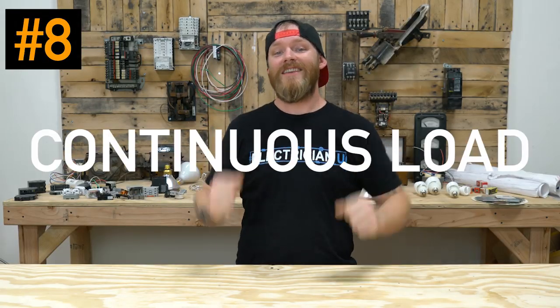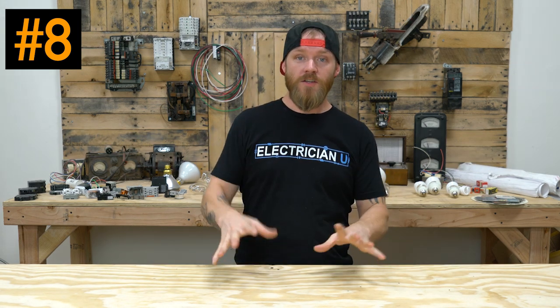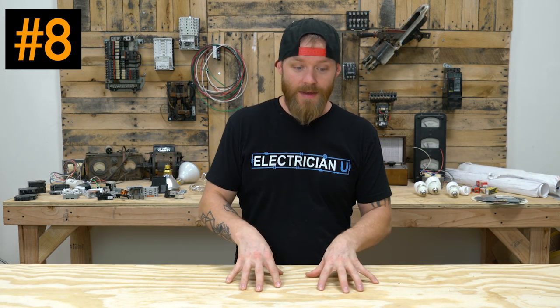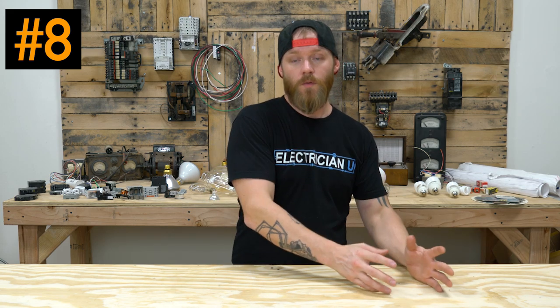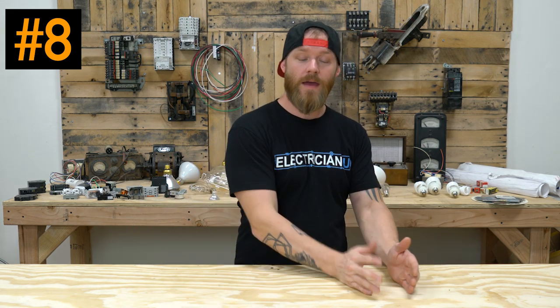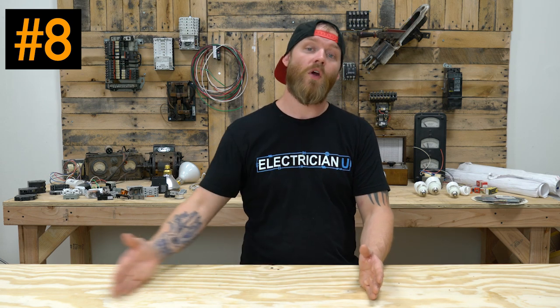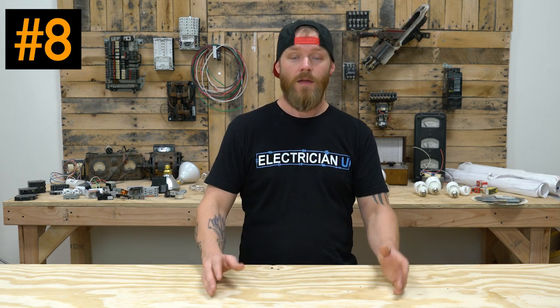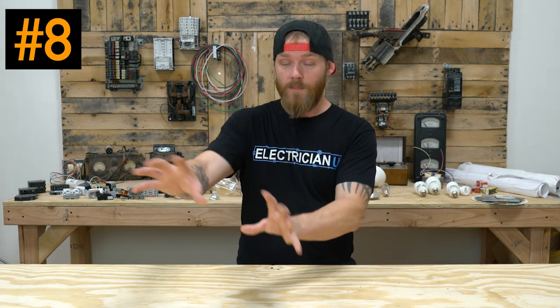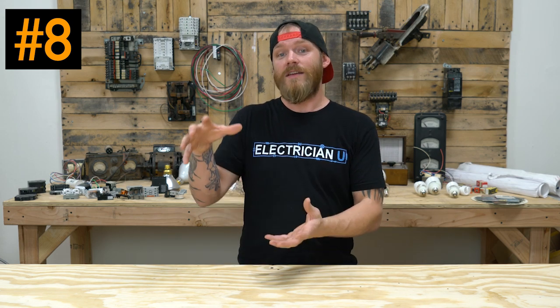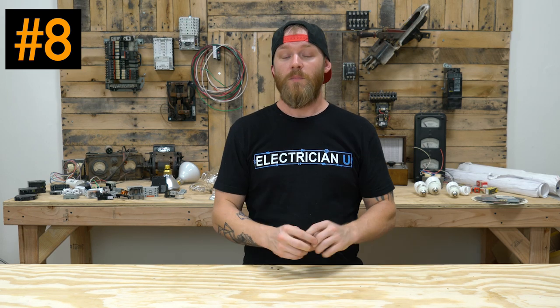Number 8 is a continuous load. Continuous loads are really important to pay attention to. A continuous load is a load, a piece of equipment, something that's going to be running, that is operating for 3 or more hours without shutting off. It's really important to know that equipment is going to do that, because the conductors can actually overheat. You can start breaking down insulation. So you have to upsize your conductors. There are different things for breakers and fuses and conductors that continuous loads come into play on. But just know it's anything more than 3 hours.